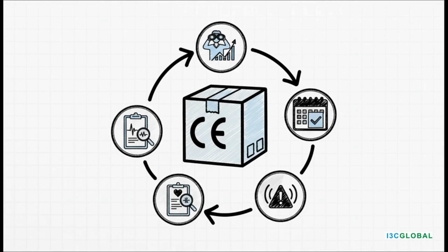And I really have to stress this. Getting that CE mark, that's not the finish line. In a lot of ways, it's actually the starting pistol. The IVDR puts this huge emphasis on post-market surveillance. That means you have an ongoing job to actively monitor how your device is doing out in the real world. You'll be submitting regular safety reports, reporting any incidents right away, and just constantly collecting data to make sure your device stays safe and effective for its entire life.